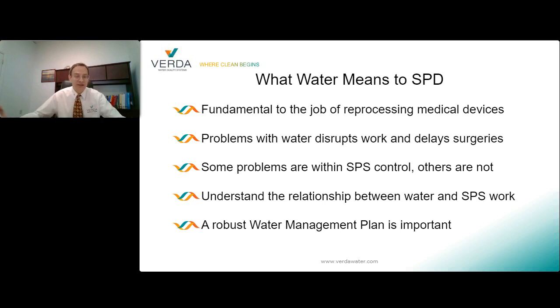This can cause surgery delays and cancellations. If the reprocessing equipment has mixing valves, the ability to adjust blended water temperature may be within the SPD or within the facility's maintenance department to control. If there is hardness in the water, that may be something the facility is controlling with water softening. The facility's hot water, for instance, may be softened, while its cold water may not be. The facility's water pH may not be something the facility can control or adjust.